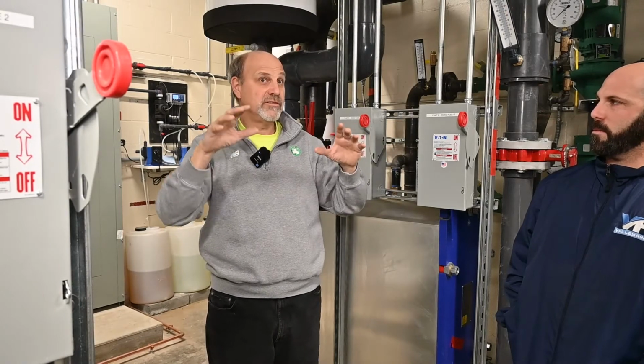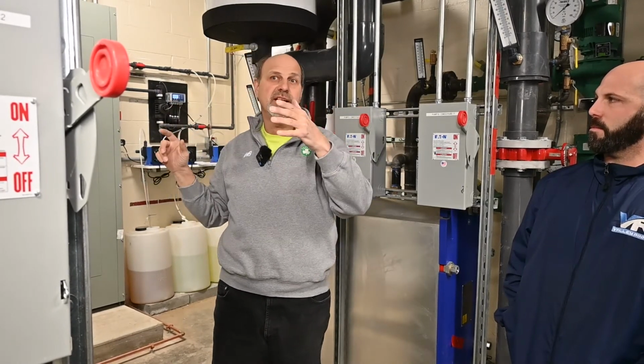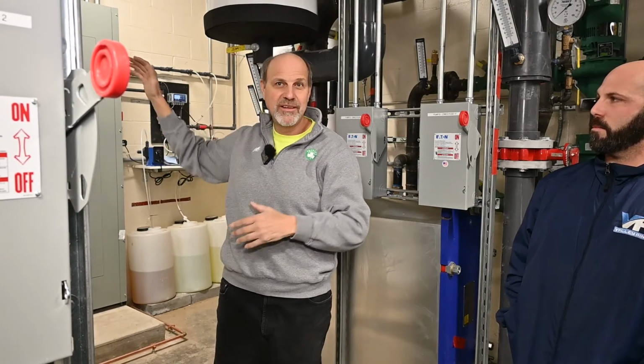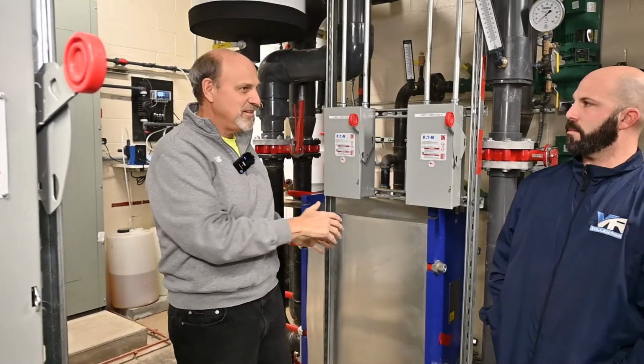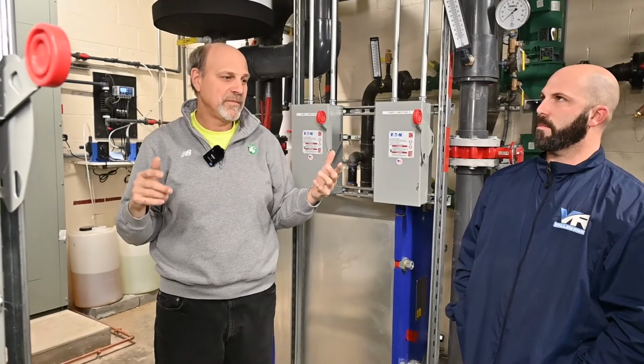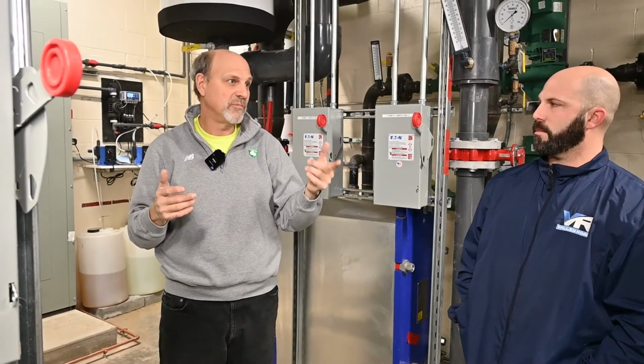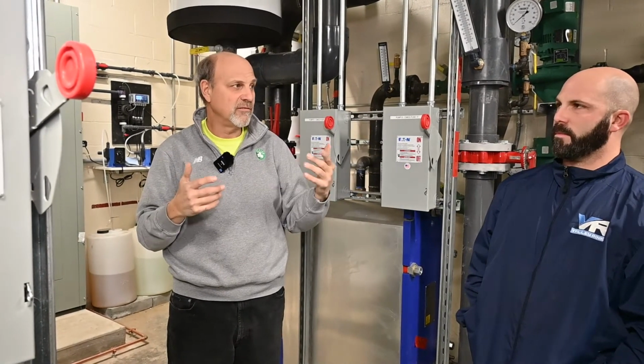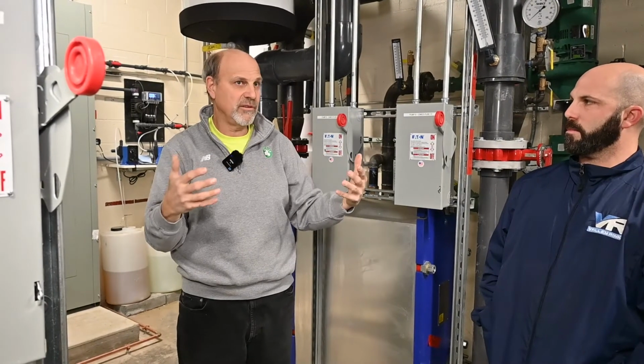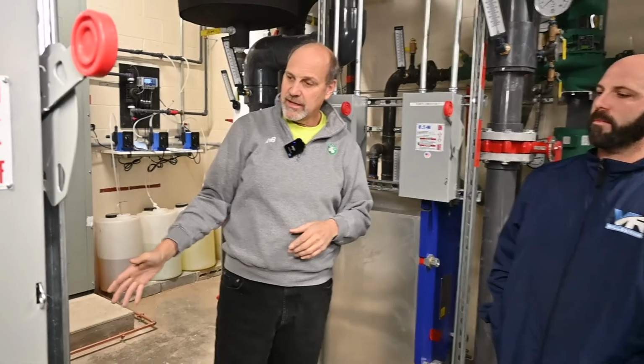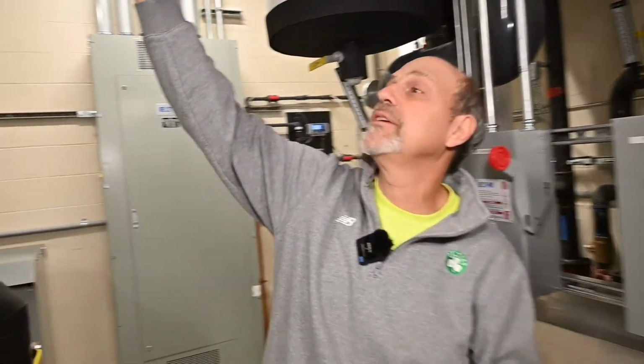For Carl, it is to commission the system in the sense of getting the right refrigerant flows in the chillers, as well as temperatures out to your rink, your cooling tower, your heat exchangers. So he's commissioned all that. I'm going to be sending out his certified report, which he sent me yesterday. Got to review it. I'll send it out to the team so that everyone has a copy of that. But in essence, cold glycol is coming back here, goes up through the pumps, tees together.